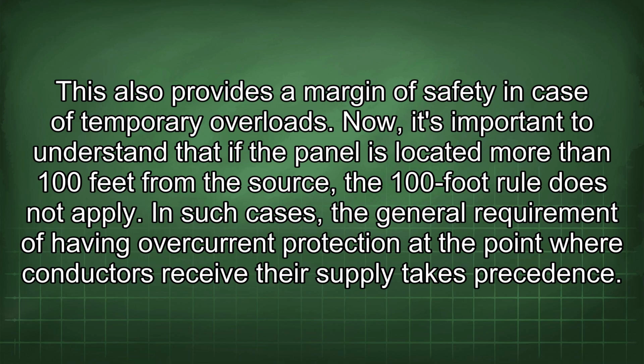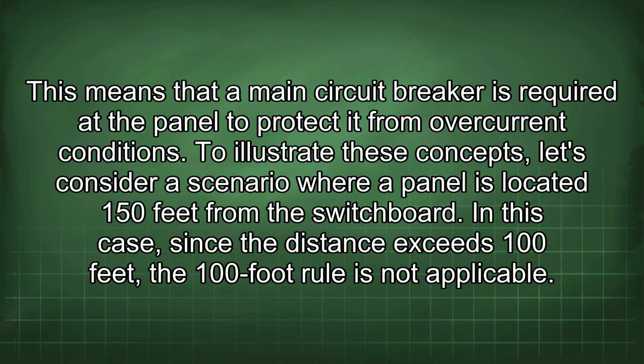Now, it's important to understand that if the panel is located more than 100 feet from the source, the 100-foot rule does not apply. In such cases, the general requirement of having overcurrent protection at the point where conductors receive their supply takes precedence.